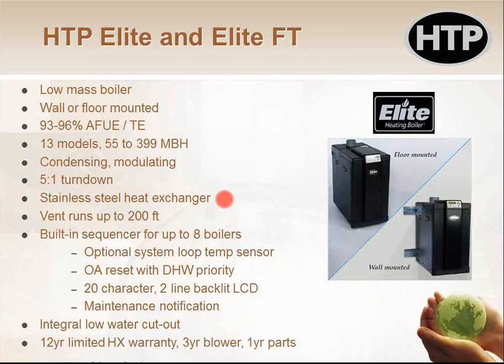And that controller does a couple things standard out of the box. It can automatically sequence 8 boilers. So here I got 2 boilers on my screen. I can connect them with a data cable and tell this guy he's number 1, tell this guy he's number 2, and then the number 1 will decide when to run each one. So maybe he'll be the lead boiler for a couple days, then the other one will be the lead boiler for a couple days, then number 3 will get a few days, number 4 will get a few days. If the lead boiler can't keep up, he'll decide when to bring another boiler on. He'll decide if it's more efficient to run 3 boilers at 60% versus 2 boilers at 100, or whatever the math comes out to. So all that's built in. You just literally connect them with a cable and say you're number 1, you're number 2, you're number 3, etc.